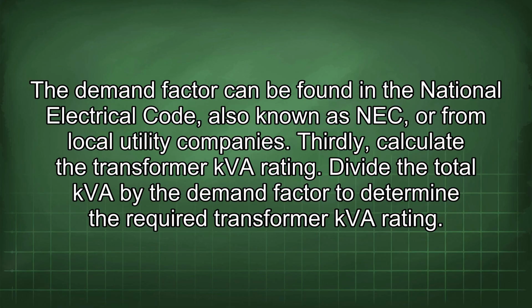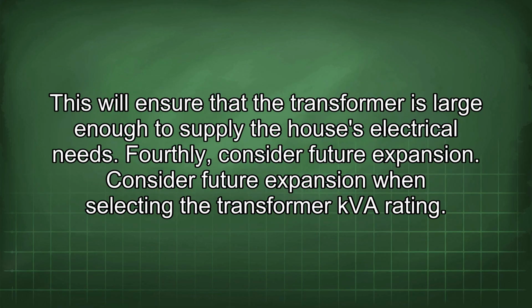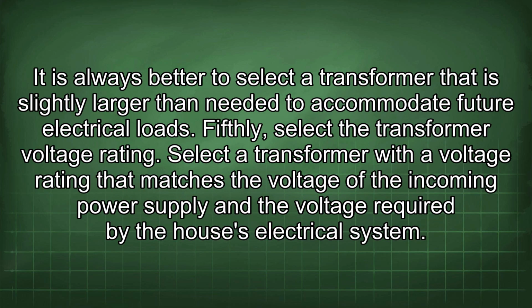Thirdly, calculate the transformer kVA rating. Divide the total kVA by the demand factor to determine the required transformer kVA rating. This will ensure that the transformer is large enough to supply a house's electrical needs. Fourthly, consider future expansion. Consider future expansion when selecting the transformer kVA rating. It is always better to select a transformer that is slightly larger than needed to accommodate future electrical loads.